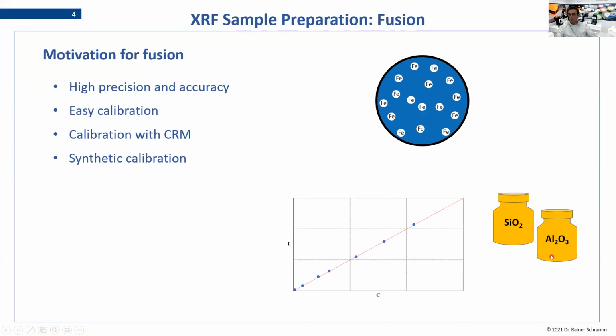The other advantage is that we can use pure chemicals to design our calibration beads, and in this way we can fill gaps we wouldn't be able to fill in a press pellet. So both the ease of calibration and the high precision, because it's a very homogeneous sample, give us the motivation to do fusion. Additionally, automation is an argument, like we do it in the FLUXANA fusion machines: we calibrate each machine for temperature, so you can guarantee that in every laboratory a FLUXANA machine gives the same beads, and you can transfer calibrations from one lab to the next. This makes the whole technology very flexible, and it also reduces development costs and time.